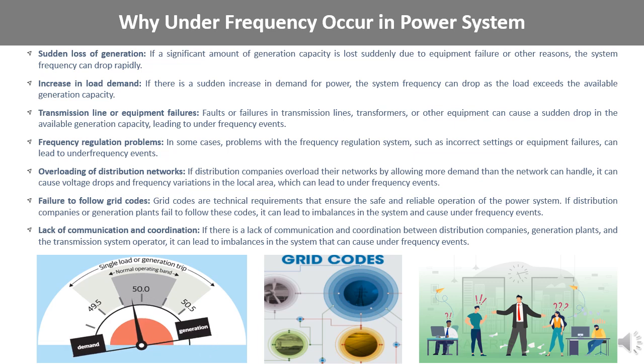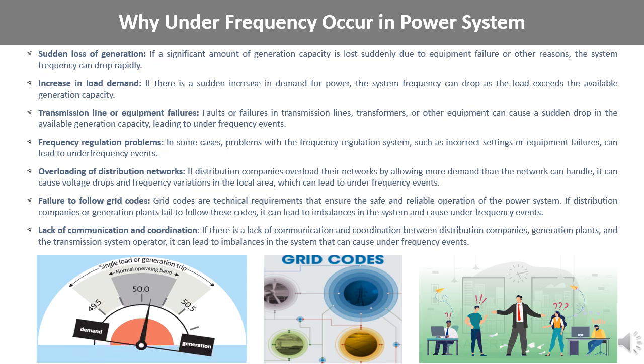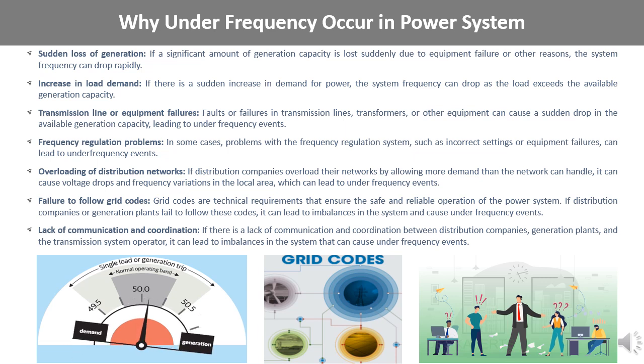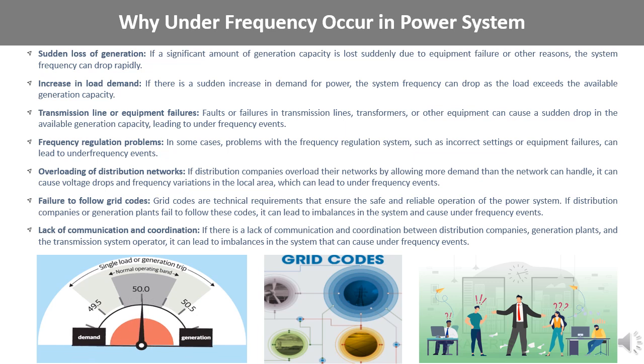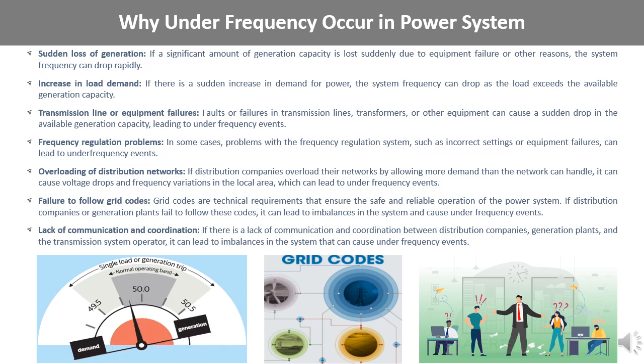Faults or failures in transmission lines, transformers, or other equipment can also lead to under-frequency events, causing a sudden drop in available generation capacity and frequency variations. In some cases, problems with the frequency regulation system, including issues with equipment settings or equipment failures, can lead to under-frequency events. Overloading of distribution networks is another potential cause — if distribution companies allow more demand than the network can handle, it can cause voltage drops and frequency variations in the local area. Grid codes are technical requirements that ensure the safe and reliable operation of the power system, and failure to follow these codes can lead to imbalances and under-frequency events.